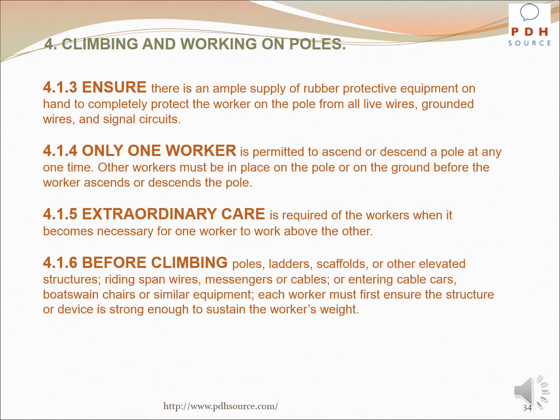Ensure there is an ample supply of rubber protective equipment on hand to completely protect the worker on the pole from all live wires, grounded wires, and signal circuits. Only one worker is permitted to ascend or descend a pole at any one time. Other workers must be in place on the pole or on the ground before the worker ascends or descends the pole. Extraordinary care is required of the workers when it becomes necessary for one worker to work above the other.